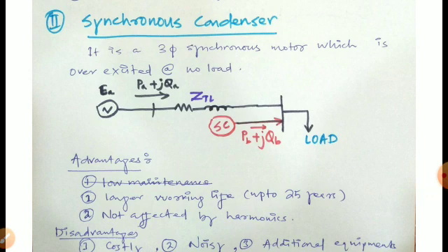So to run a motor in leading power factor, we have to provide excess excitation, that is called overexcitation, and no load is connected to the shaft of the synchronous motor. Then the motor will supply reactive power to the system. So it behaves like a capacitor.